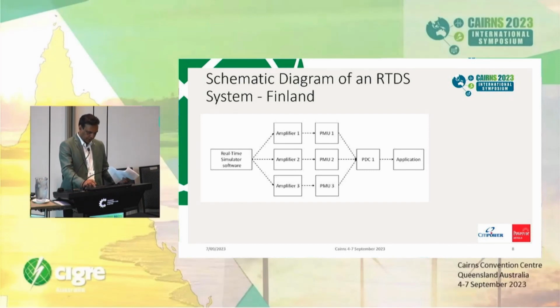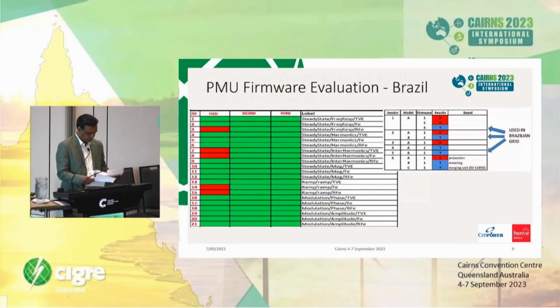Then the next example is from Brazil. You can see the columns first, second, and third. This is the attempts taken by the PMU to fall within the accuracy requirements of the IEEE C37.118 standard. For example, with ID number 3, the PMU failed on the first attempt, but then some software or hardware modifications were made by the manufacturer to make it compliant with the accuracy standards, and it passed in the second and third attempts.